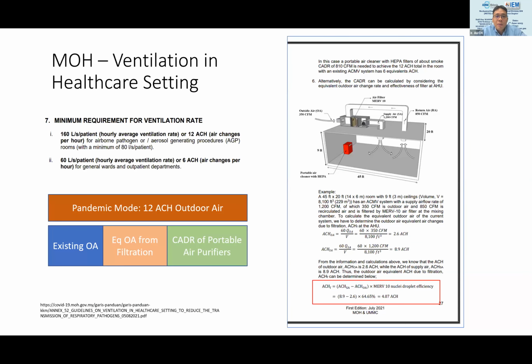The MOH setting is similar, talking about 12 air changes per hour, which is actually related to outdoor air as well—just explained in terms of room volume change, using room size as a standard to compute the required outdoor air. So you have existing outdoor air provision plus equivalent outdoor air from filtration—if you cannot dilute, you clean it by trapping the virus, and add both together. If that's still not enough, you need to add portable air purifiers.